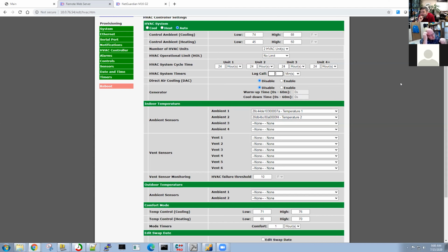We had that one in Bakersfield freeze over. We put it up the first night and you get to these weird equilibrium points where you're able to cool it down—it keeps it below 88, but it hung at 84 and never got down to 74. So that's why we had to change it to kind of a momentum factor: if we're not making headway after the 1 minute or 5 minute or whatever setting you have, then it's eligible to do the lag.